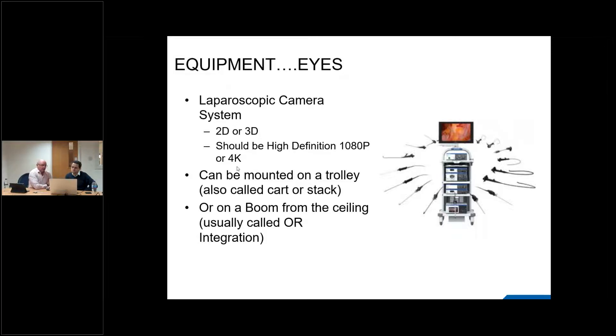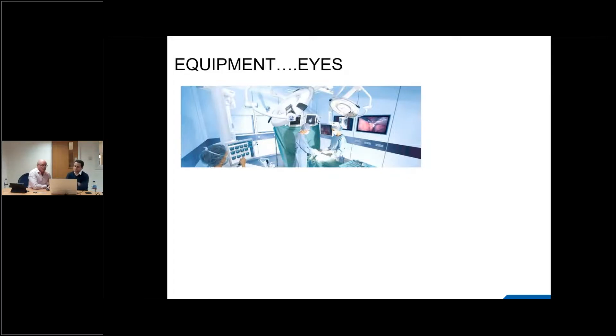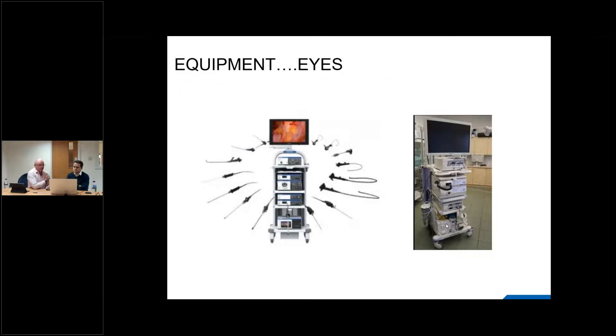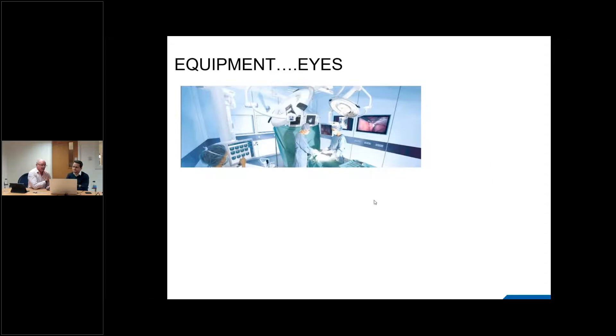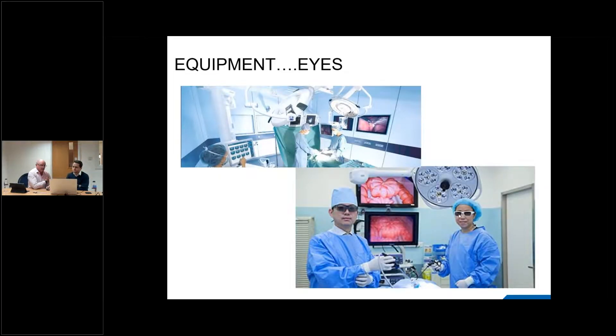The laparoscopic system is typically mounted on a trolley — also called a cart or stack — or can be ceiling-mounted on booms with monitors on the booms and walls, which is a more ergonomic design. Ceiling-mounted systems can't be transported between theatres, while trolley-based systems can. 3D systems require the surgeon to wear glasses, and there are strong proponents of both 2D and 3D systems. Robotic laparoscopic surgery is also available.